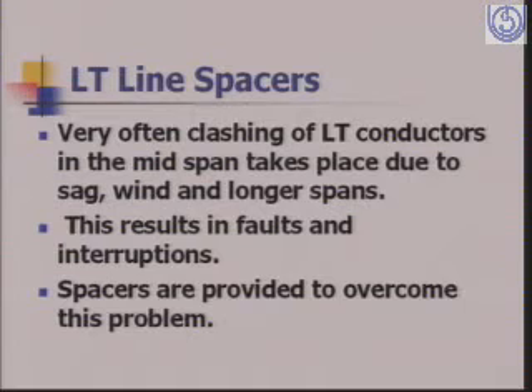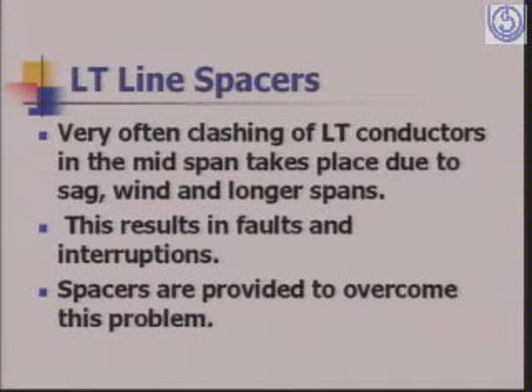Then we use the LT line spacers. You must have seen sometimes wooden spacers or otherwise also. So these spacers are used to prevent clashing of LT conductors in the mid-span due to sag, wind, and longer spans. This could result in faults and interruptions, and therefore spacers are provided to overcome this problem. You may have seen these spacers if you look at an LT line on the road.